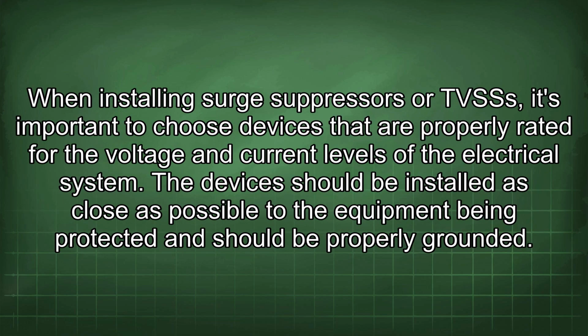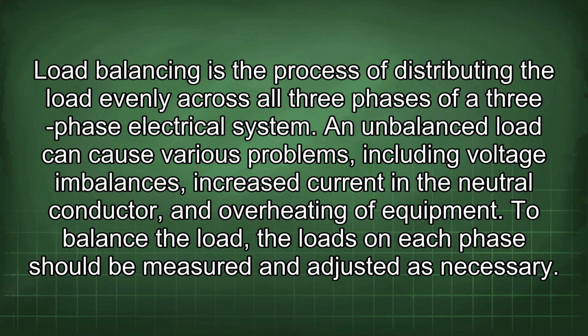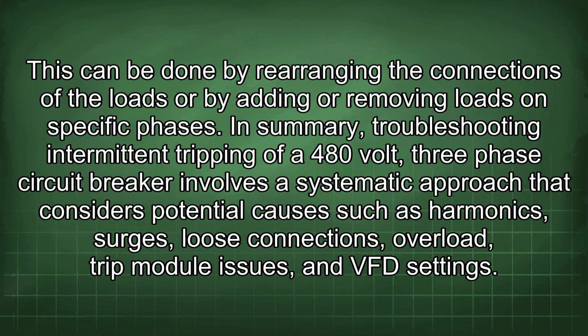When installing surge suppressors or TVSSs, it's important to choose devices that are properly rated for the voltage and current levels of the electrical system. The devices should be installed as close as possible to the equipment being protected and should be properly grounded. Load balancing is the process of distributing the load evenly across all three phases of a three-phase electrical system. Unbalanced load can cause various problems, including voltage imbalances, increased current in the neutral conductor, and overheating of equipment. To balance the load, the loads on each phase should be measured and adjusted as necessary. This can be done by rearranging the connections of the loads or by adding or removing loads on specific phases.